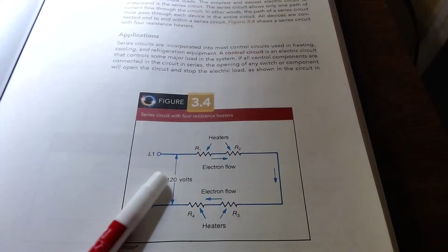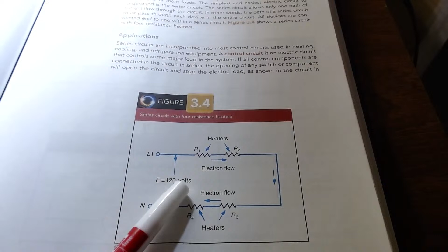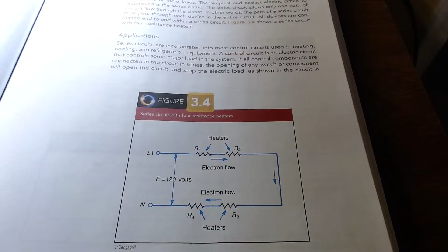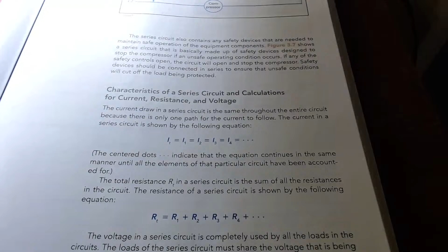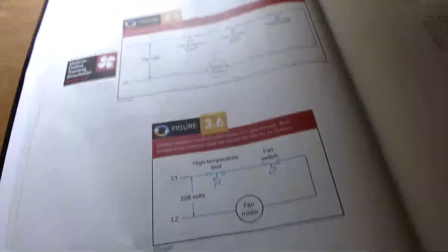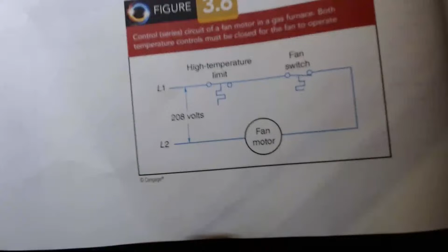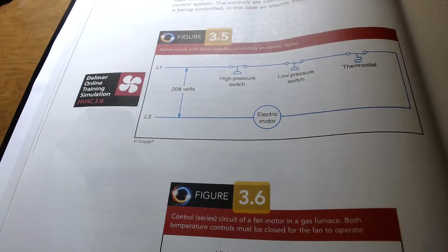So L1, your electron flow is going through your heater, back through your other side of your elements, back to ground. You know, this says 120, but figure this is 240. Okay, this is where your heat strips come into play. And yes, this does say 208 volts. And yes, you can have high voltage pressure switches and thermostats. Just because it's on a system doesn't mean your control voltage is always 24 volts.